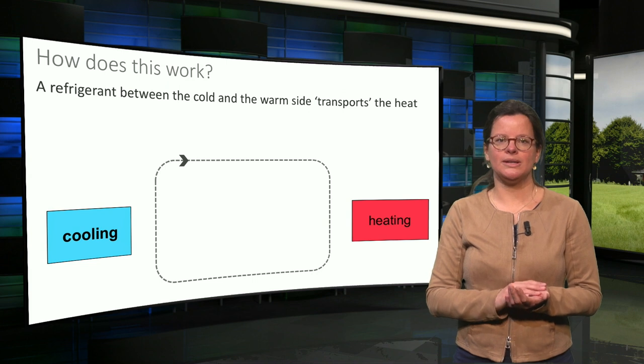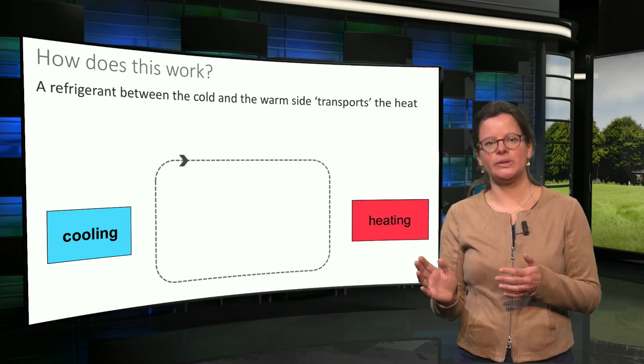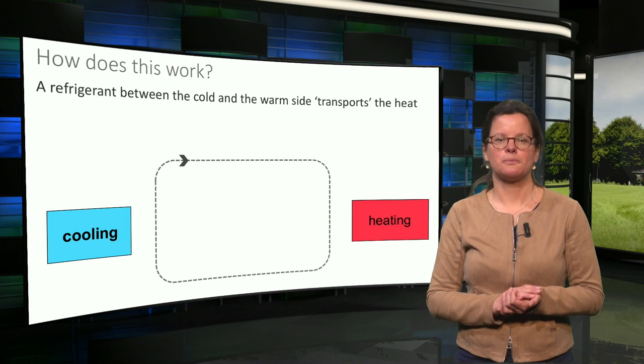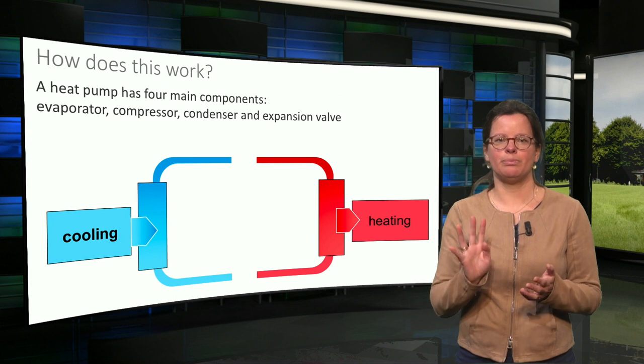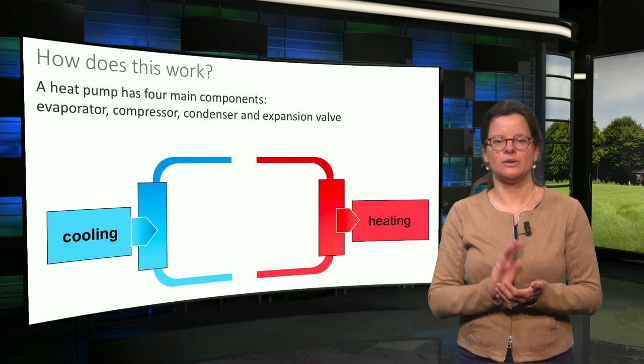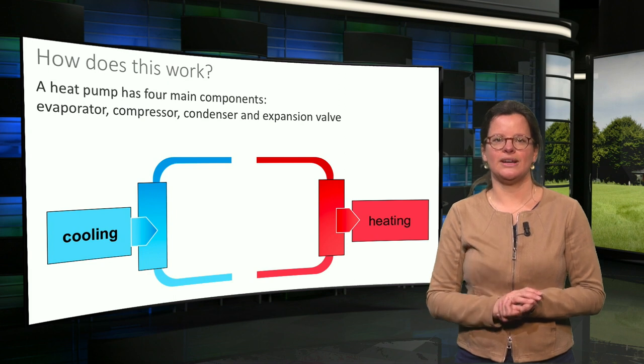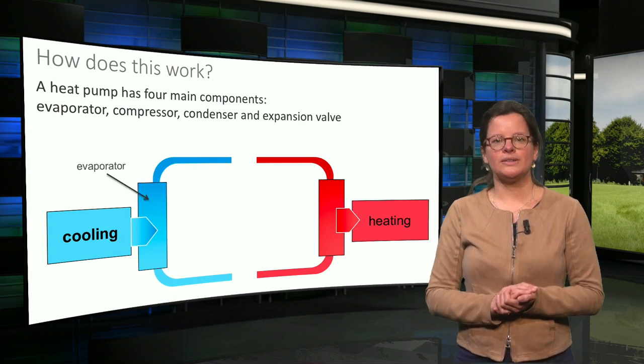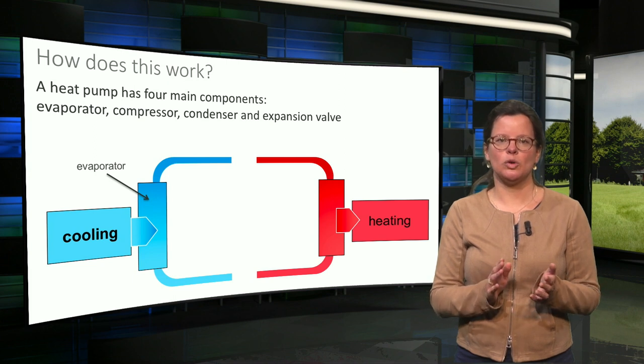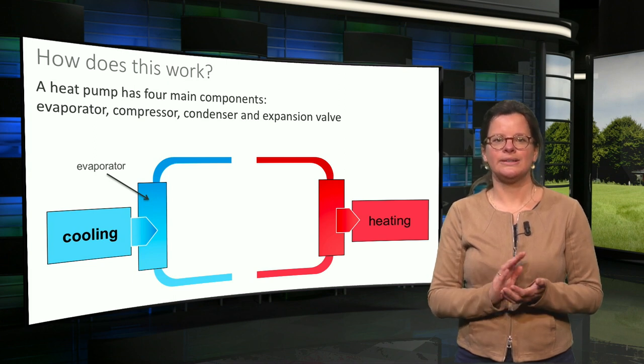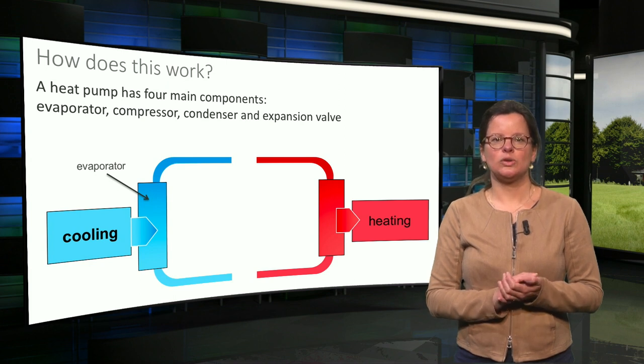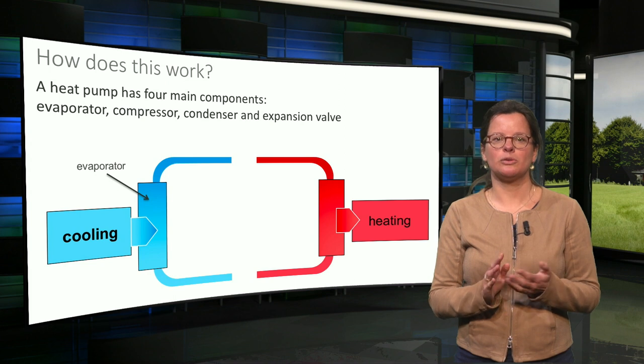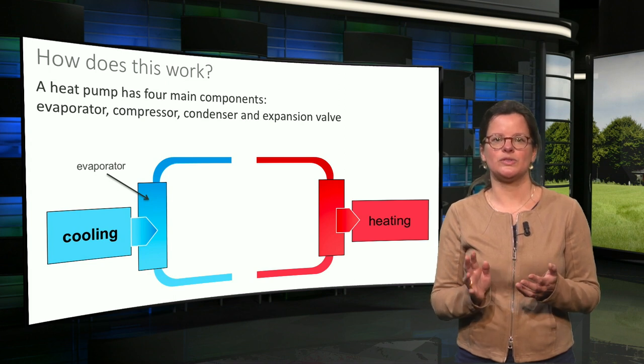The refrigerant or working medium undergoes a cycle from liquid phase to gas phase to liquid, and so on. To be able to transfer the heat from the cold to the warm side, a heat pump has four main components: evaporator, compressor, condenser, and expansion device. The evaporator is a heat exchanger where heat is transferred from the cold body to the refrigerant, meaning the refrigerant must be colder than the cold body, which means cooling of the cold side takes place. This heat exchanger at the cold side is called the evaporator as the working medium is converted from liquid phase to gas phase as a result of the heat transfer.